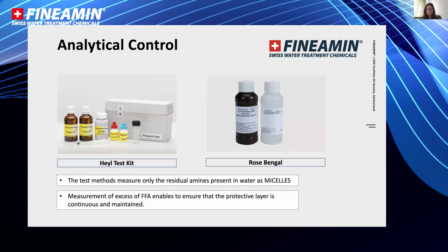Okay, so this molecule, film-forming amine, is a special molecule. Definitely one may think, okay, we are using it, but what should we do in order to control that molecule analytically? There are different methods. Again, measuring some organic molecules is not very easy, but it also depends on the practice, I would say. There are very well-known methods, and two of them: one is titrimetric, known as the Heyl method, and the other is spectrophotometric, Rose Bengal. Basically, we are measuring the excess. As we do in other treatments, we have the film formed, and there will be some excess molecules in the system. Through this analytical control, we measure that excess, so that we are sure the protective layer is there, continuous, and maintained.